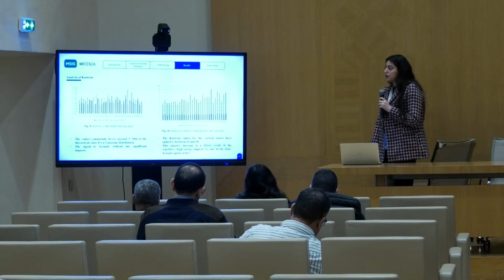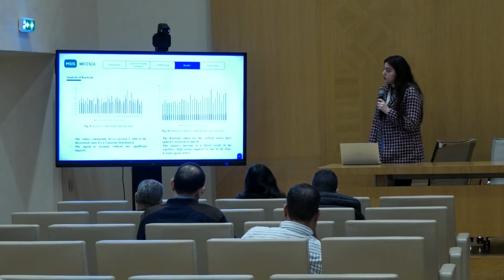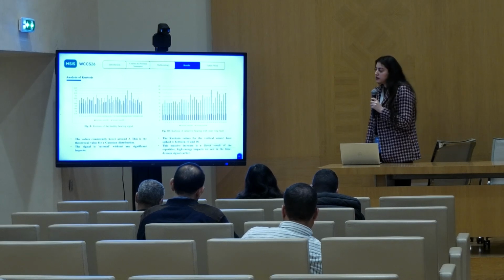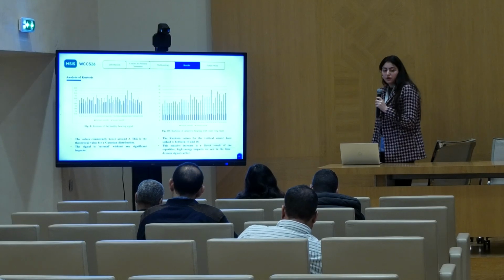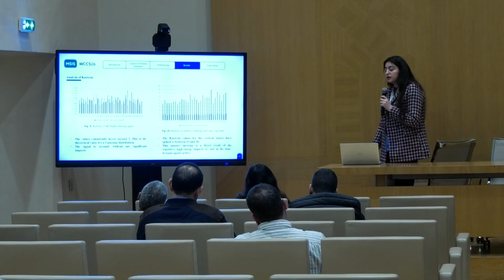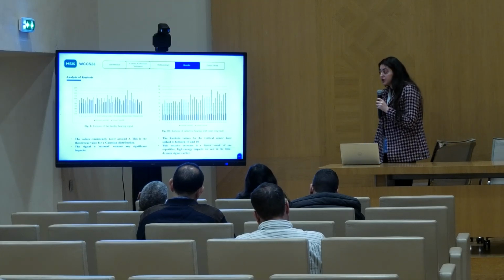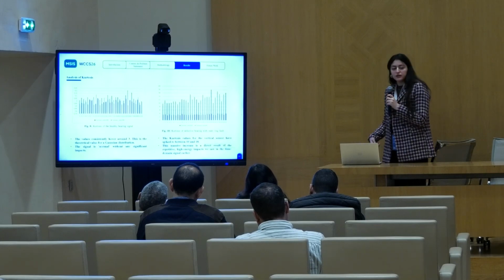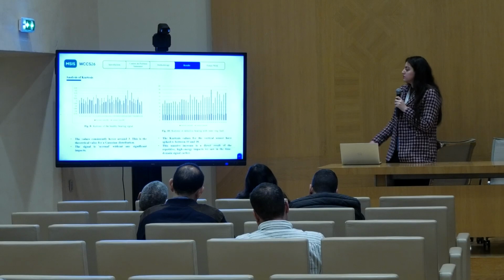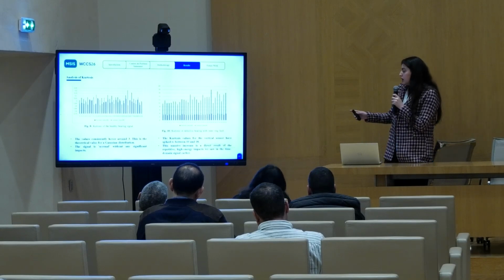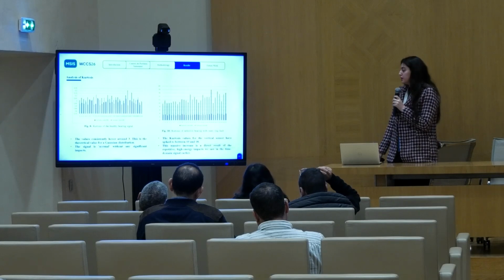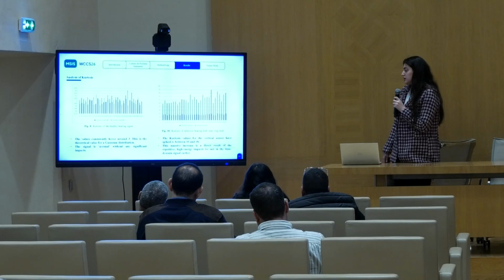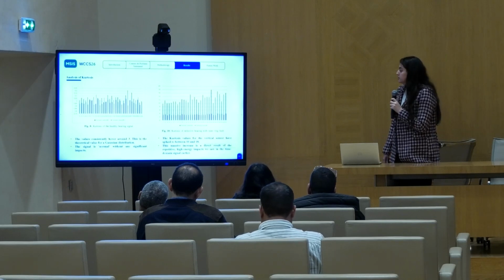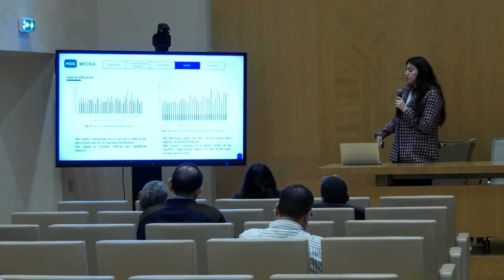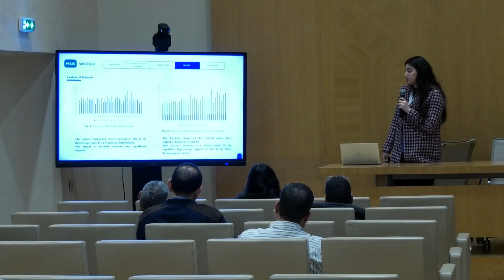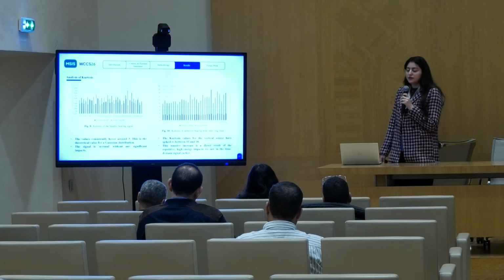Here we move on to the kurtosis analysis. On the right side, we have the kurtosis analysis of the healthy bearing. The values consistently hover around 3, which is the value for a Gaussian distribution. And we can say that the signal is normal without any significant impact. However, on the left side, the opposite, we have the kurtosis analysis of an outer ring fault. The values are between 10 and 18 for the vertical sensor, and we can say that this massive increase is a direct result of the repetitive high energy impacts we saw in the time domain earlier.